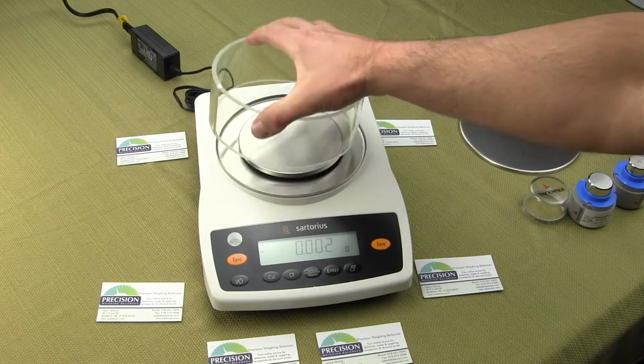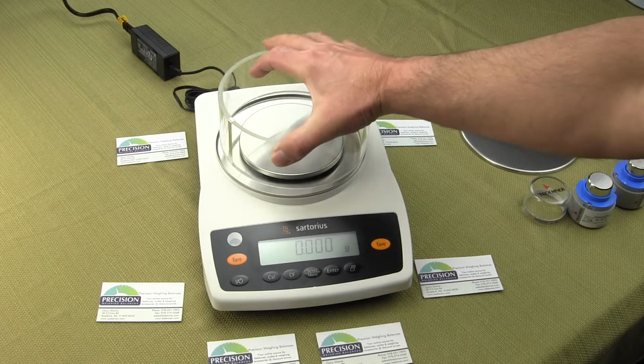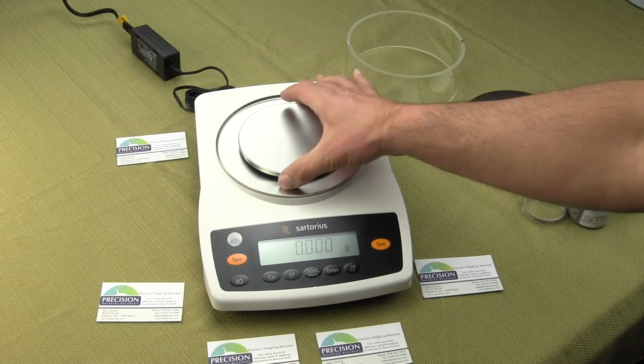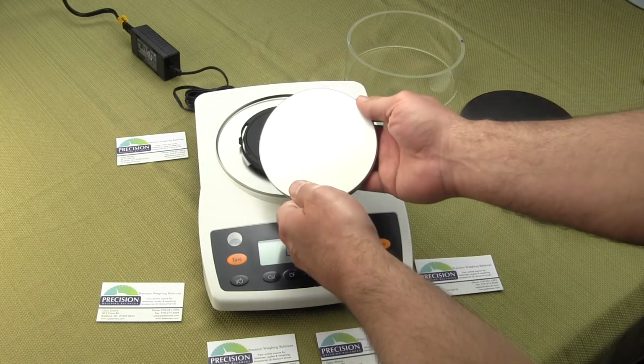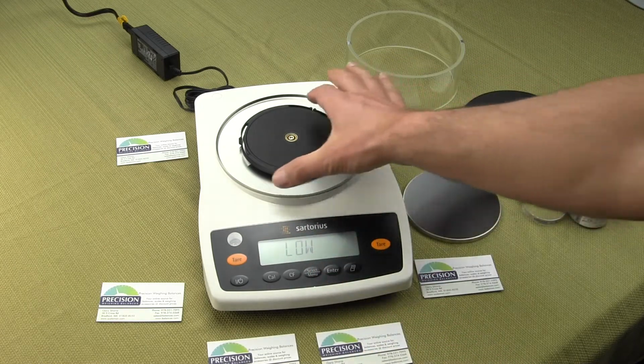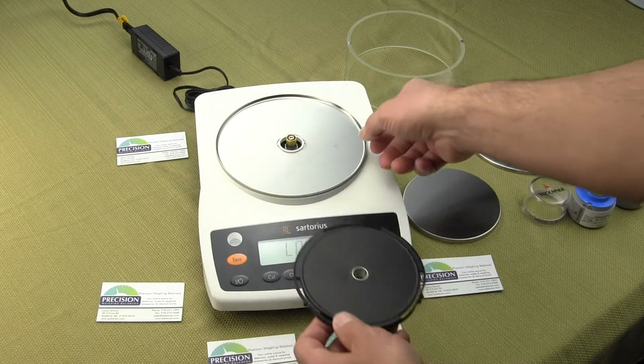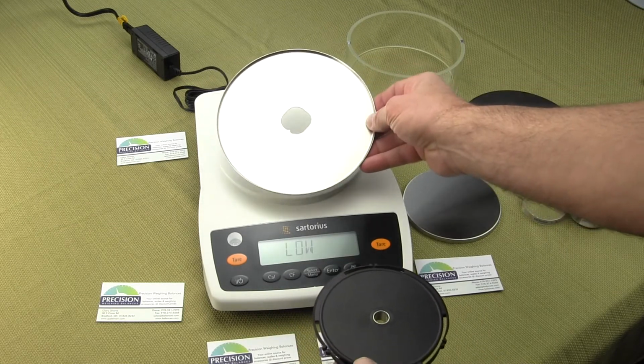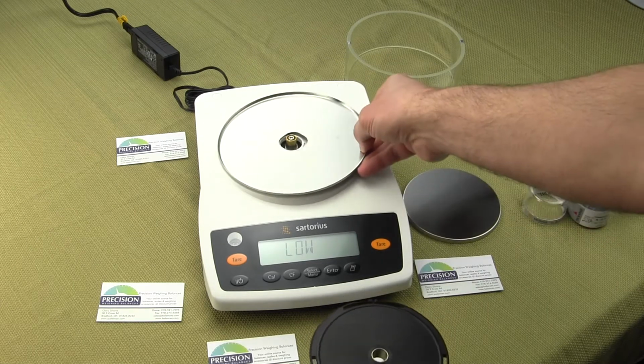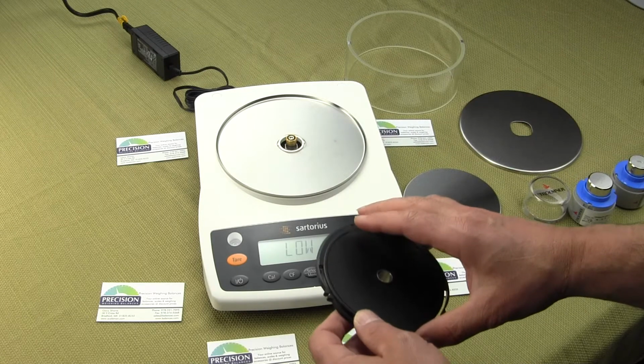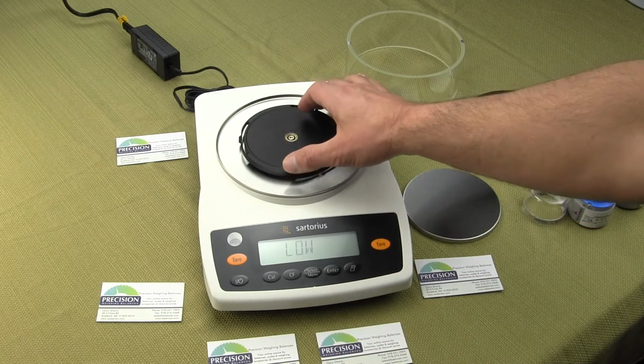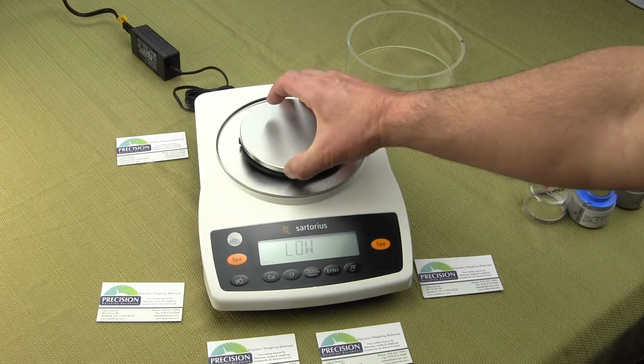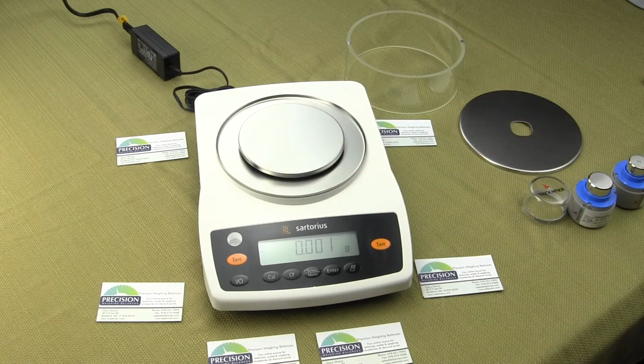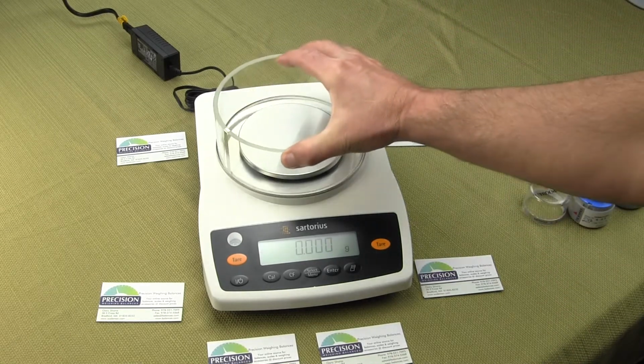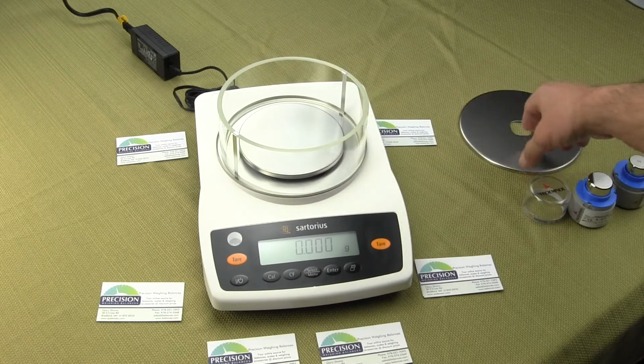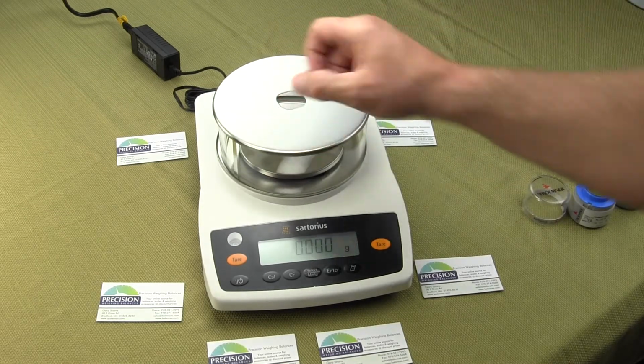The draft shield has a circular glass draft shield, and then we have a 4.5-inch stainless steel platform, and then there's a pan support, and beneath that we have the stainless steel splash guard. So this Sartorius balance is very easy to assemble. When you get it, all you have to do is put on the lower splash shield, your pan support, your 4.5-inch diameter weigh-in platform. And this is a glass draft shield, round circular draft shield. And then you have your stainless steel top.